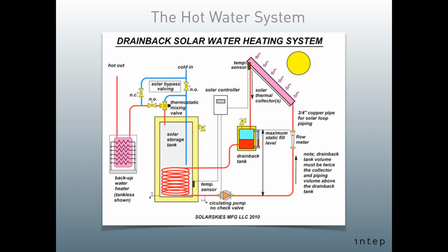And then attached to the storage tank is an on-demand electric backup booster. So if there's ever not enough, or the owners decide they want to take a dozen showers one after the next, there's essentially endless heat coming through the system, because we have an on-demand water heater that can heat city water temperature to full temperature, or anything in between that and what the tank has. So as long as we have electricity, we'll never run out of hot water. And that's a great way to avoid some of the primary energy once more. Again, 85% is being delivered here through the sun.